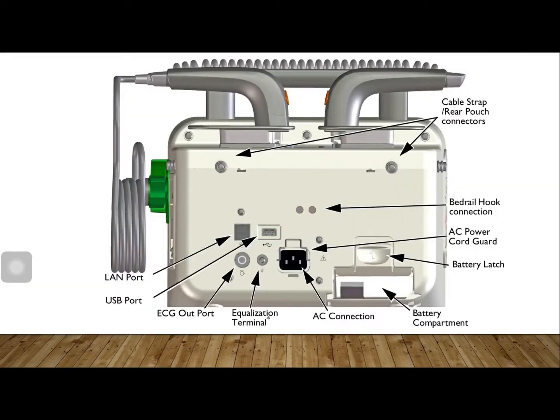At the back part, we have the LAN port, USB port, ECG out port, equalization terminal, AC connection, and battery compartment. Our battery is lithium ion. Charging time is 3 hours. Maximum operational time if fully charged is 100 full energy shocks or 2.5 hours of continuous monitoring. Battery latch, AC power cord guard, bed rail hook connection, cable strap or rear pouch connectors. So these are the ports at the back part.